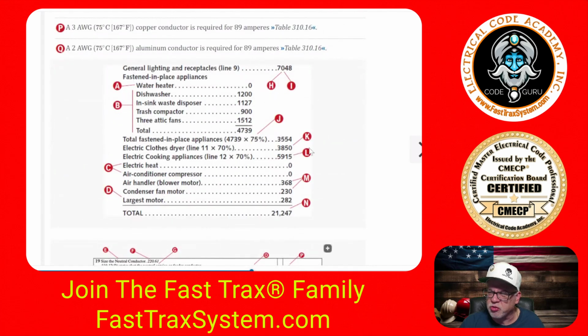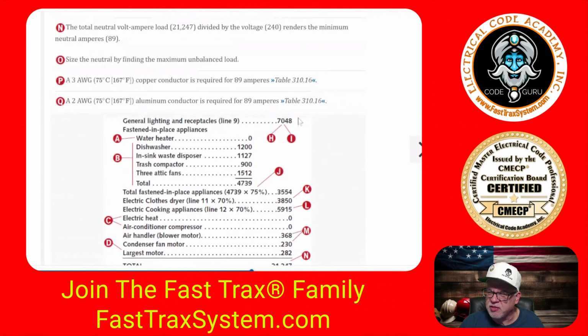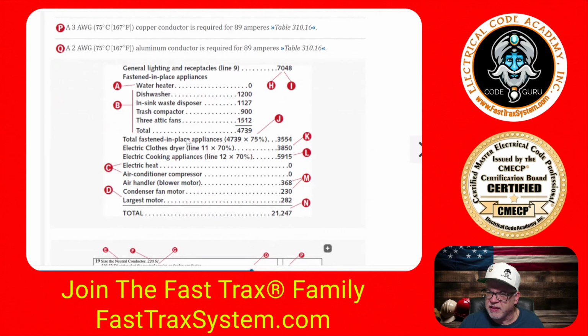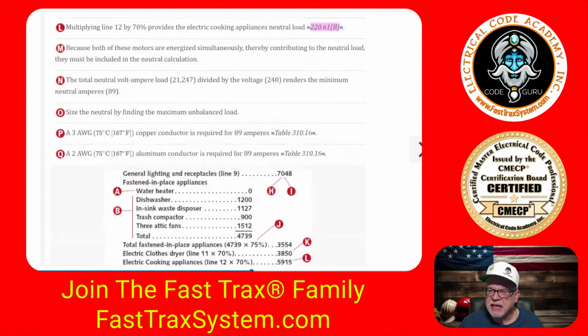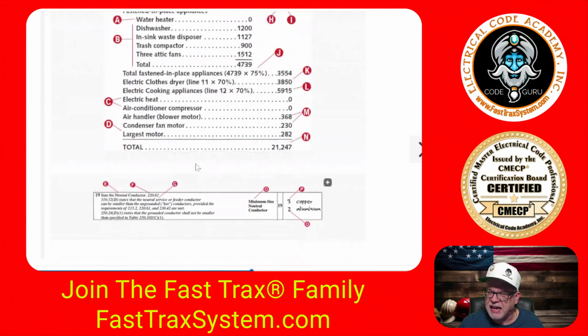N is the total summation. So we added up this value. We added here the value after the 75% for the appliances, this value, this value, this value, and these values. And we got 21,247. You divide that by 240. And here you'll see that ultimately that comes up with 89 amperes.